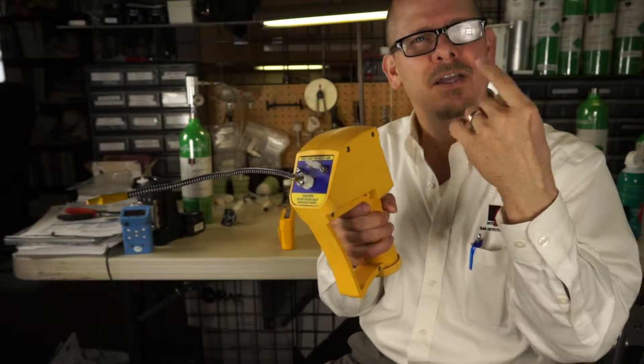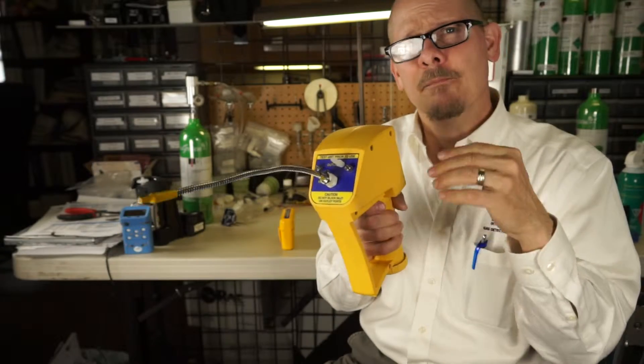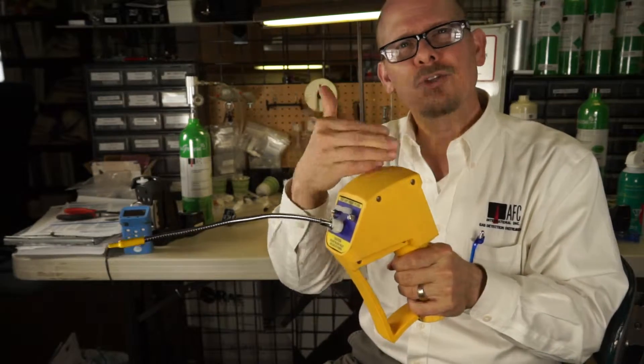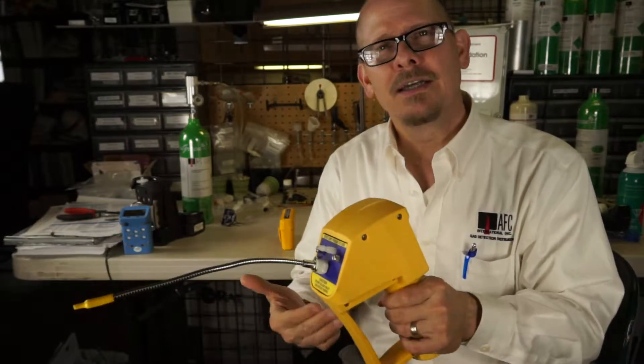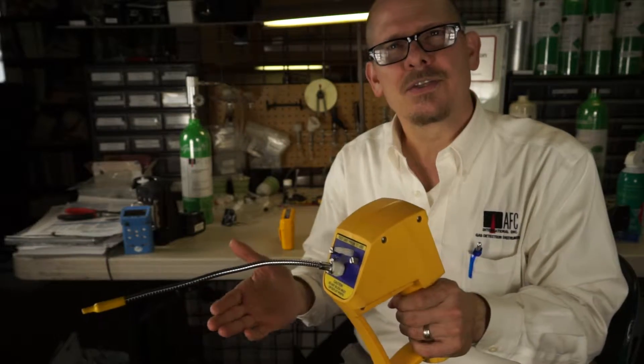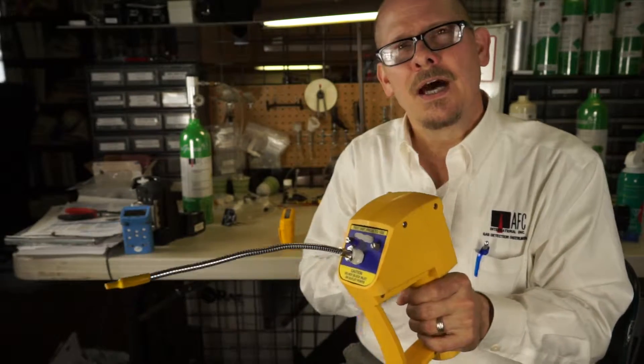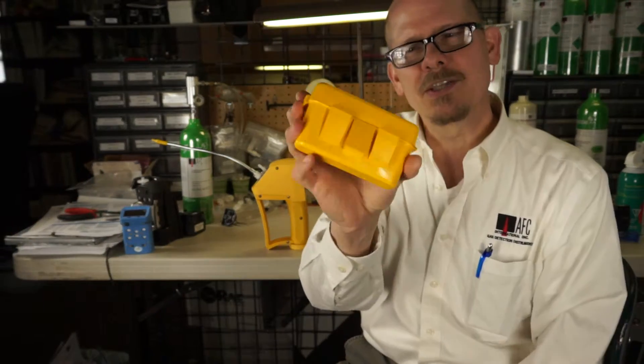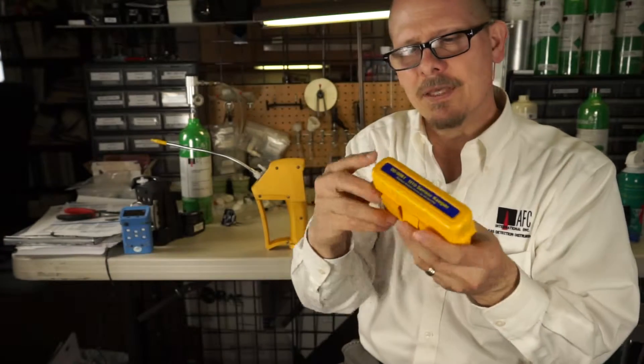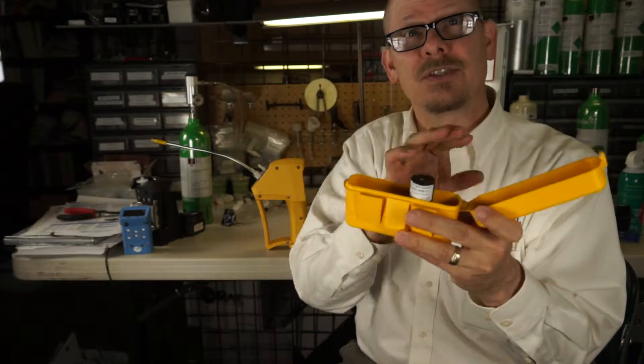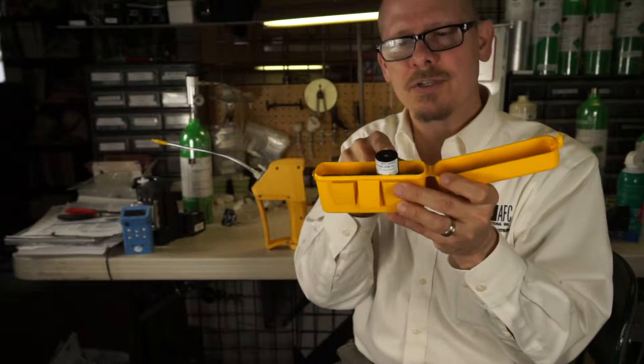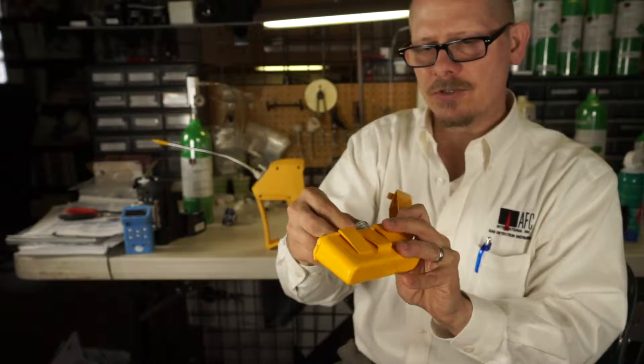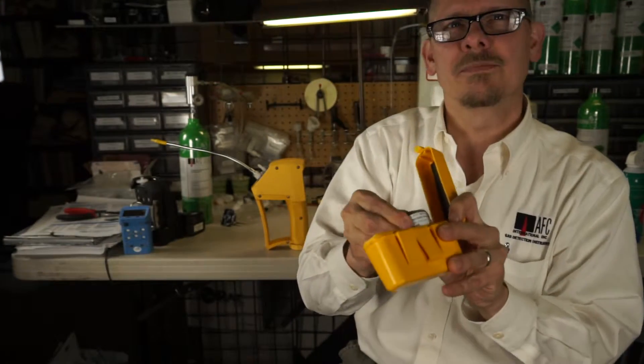Single gas means it can only do one at a time, but it does use smart sensor technology so we can interchange different sensors on the fly and do a variety of different gases. I'm going to pull up the sensor keeper that comes with it. The sensor keeper is basically exactly what it means—sensor keeper. It's going to keep all your spare sensors. It has room for one, two, three, four spare sensors.